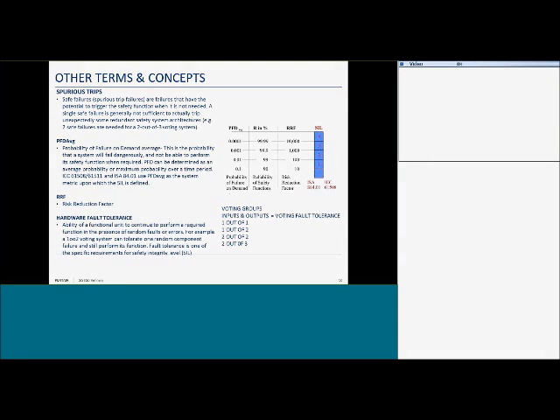When our customers are designing safety instrumented systems, they typically assign a targeted risk reduction factor. This is a target that they would like to achieve with their SIF, safety instrumented function, which is the sensors, logic solver, and final element. We can help them impact some of these areas of design by helping them develop more robust automated packages that have less likelihood for spurious trips. Spurious trips can be caused by a lot of different factors, and we're going to discuss that a little bit more coming up.